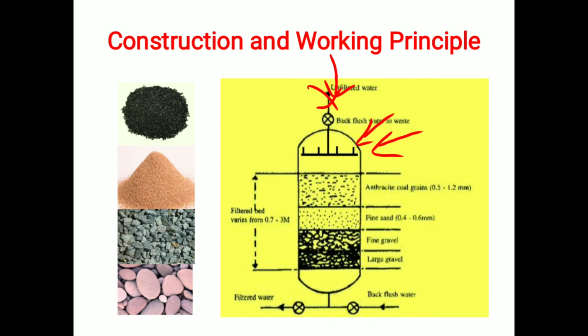Nozzles are fitted on this header, and the direction of these nozzles is upward. The reason is that if we keep the nozzles pointing downward, it will disturb the media. This is the media, so it will disturb the media. To avoid this, we keep the nozzle direction upward.